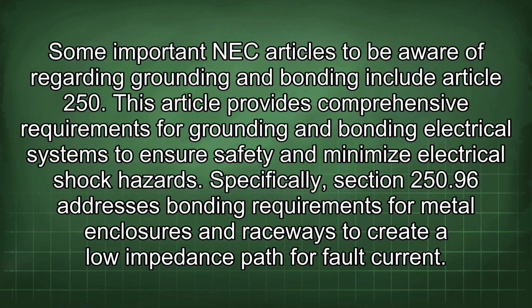Some important NEC articles to be aware of regarding grounding and bonding include Article 250. This article provides comprehensive requirements for grounding and bonding electrical systems to ensure safety and minimize electrical shock hazards. Specifically, Section 250.96 addresses bonding requirements for metal enclosures and raceways to create a low-impedance path for fault current.